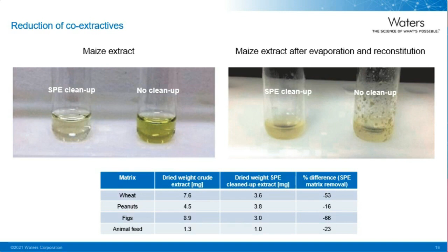In such an experiment, I evaporated 1.2 milliliters of extract of different food matrices with and without passing the extract through the SPE. I then calculated the weight percentage difference to check effectively how much solid material is being retained by the cartridge. And we go from 16% to 66% reduction of residual weight after evaporation, meaning the SPE cleanup is really doing something here. And this is important because using the cleanup, we get from 16 to 66% less solid material entering the mass spec at every injection.